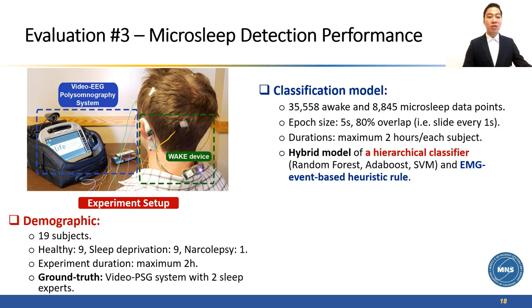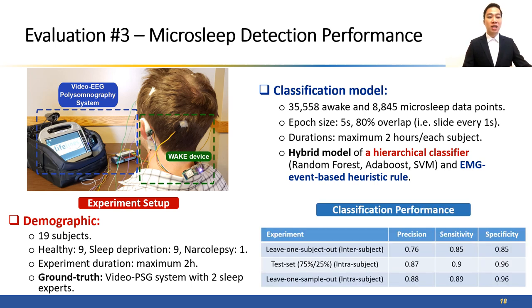In the third experiment, we evaluated the ability to detect microsleep with WAKE by conducting the Maintenance of Wakefulness Test on 19 subjects. The video EEG system and the scoring from two sleep experts were used as the ground truth. Our dataset had more than 40,000 data points. We developed a hybrid classification model to classify awake and microsleep epochs. In the leave-one-subject-out validation, our model can achieve 76% for precision and 85% for both sensitivity and specificity on an unseen subject. On a specific subject, we can achieve more than 87% for all of the metrics.